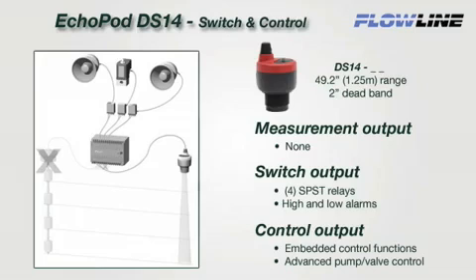The DS14 is a multi-function sensor that provides relay switch and embedded control functions only. This sensor has no measurement signal output. It's designed to replace contact switches connected to a PLC with one to four inputs. The sensor can be installed without any changes to control hardware or software. Use of the embedded relay control functions can further lower cost by eliminating or reducing the need for external PLC or simple relay control logic hardware.